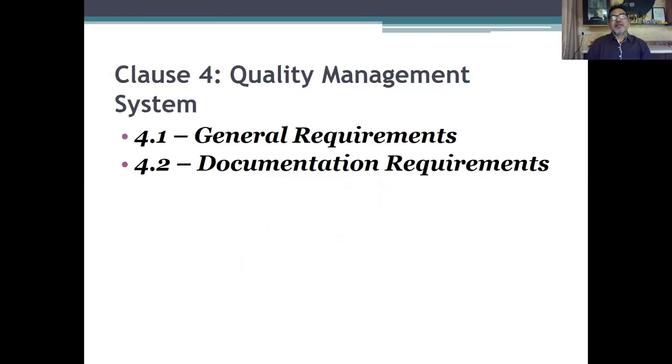Clause 4 Quality Management System. Clause 4 addresses the requirement to document procedures related to quality management processes. Documentation requirements have been expanded and clarified in the 2016 update. This is additional language that clarifies the quality management processes required by ISO 13485. It does not exempt an organization from meeting any additional quality management requirements mandated by regulatory authorities. A primary change here states that the quality management requirements now apply to any outsourced products as well as those produced by the organization itself.